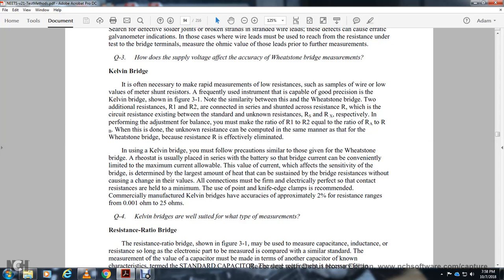When using the Kelvin bridge, a rheostat is normally placed in the circuit to limit current to the maximum allowable value, which also affects bridge sensitivity. The value of current determines the largest amount of heat that can be sustained by the bridge resistors. All connections must be firmly made to hold contact resistance to a minimum, using knife-edge clamps. Commercially manufactured Kelvin bridges have accuracy of approximately 2% over a resistance range of 0.001 ohm to 25 ohms.